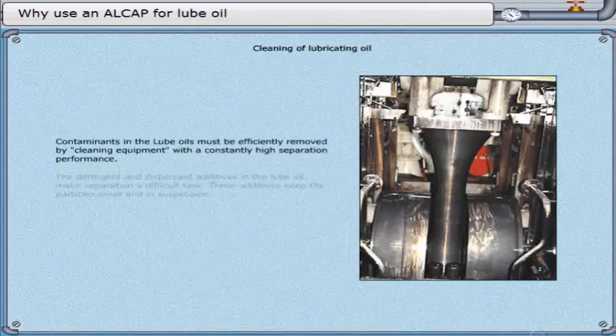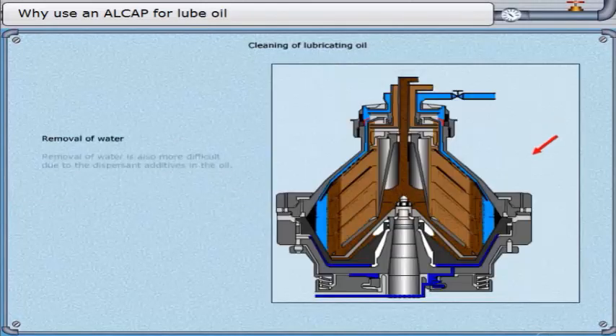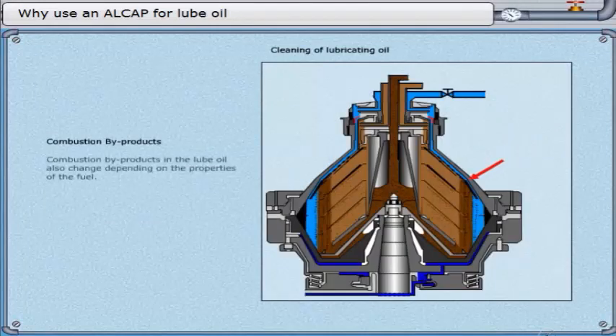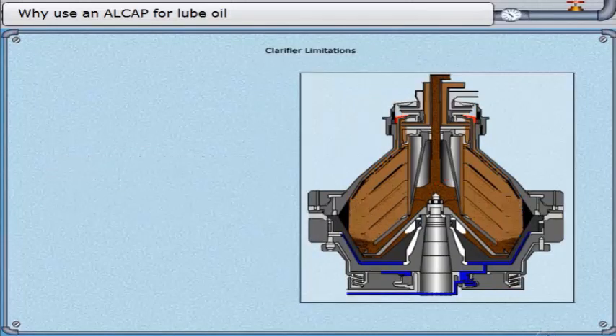Contaminants in the lube oils must be efficiently removed by cleaning equipment with a constantly high separation performance. The detergent and dispersant additives in the lube oil make separation a difficult task — these additives keep the particles small and in suspension to keep the engine crankcase clean. Removal of water is also more difficult due to the dispersant additives in the oil. In extreme cases, it is even possible that the lube oil picks up water from the water seal of a conventional purifier if the oil and water are brought into turbulent contact with each other. Combustion byproducts in the lube oil also change depending on the properties of the fuel, and separated sludge is stickier, which makes it difficult to discharge from self-cleaning centrifugal separators.